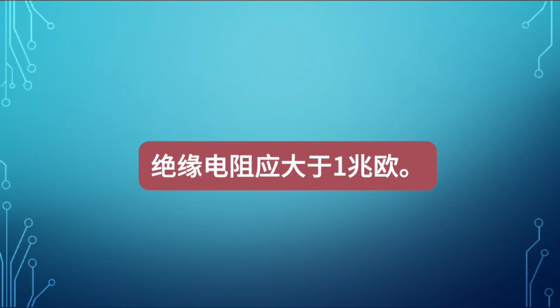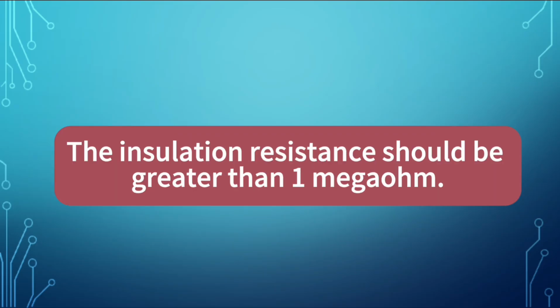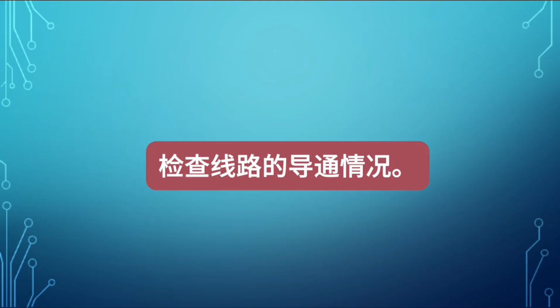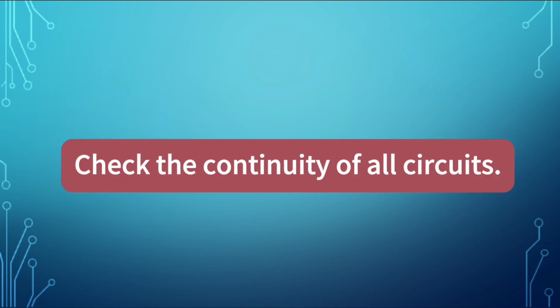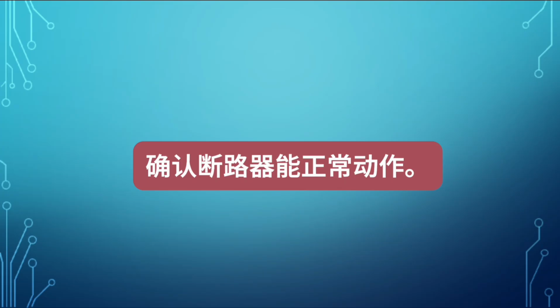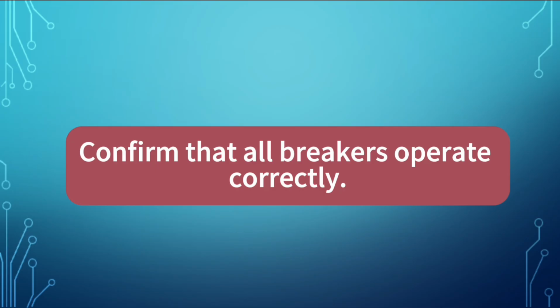The insulation resistance should be greater than 1 megohm. Check the continuity of all circuits. Confirm that all breakers operate correctly.